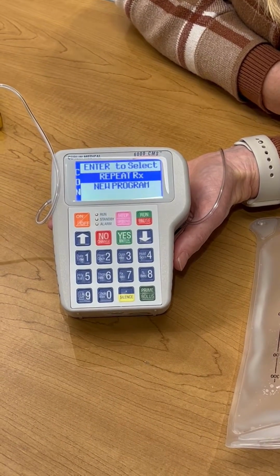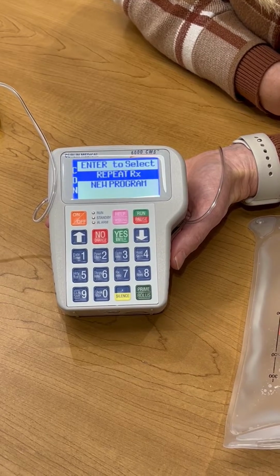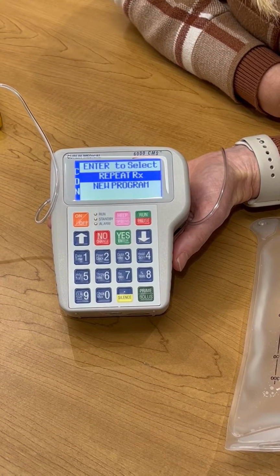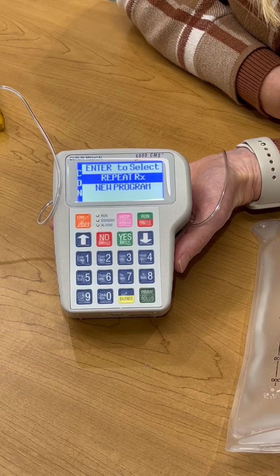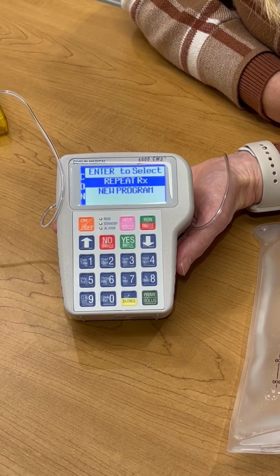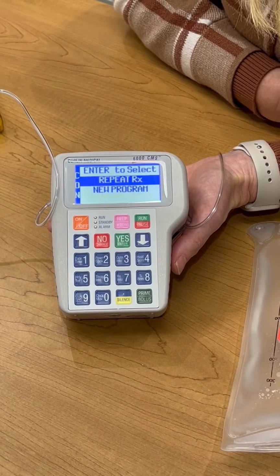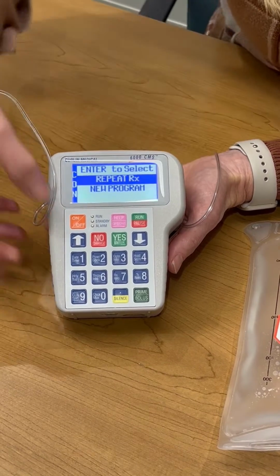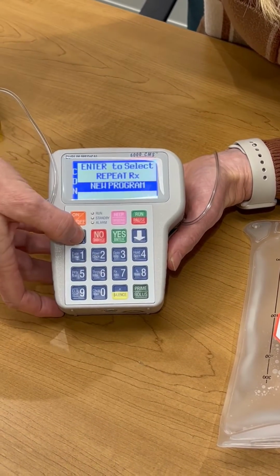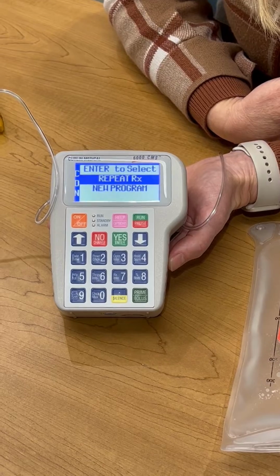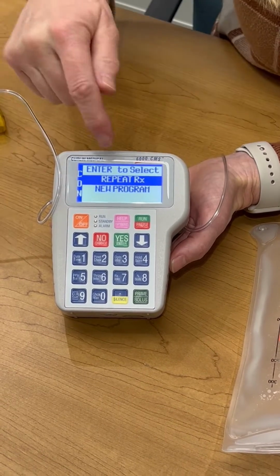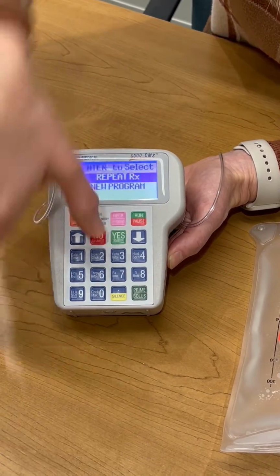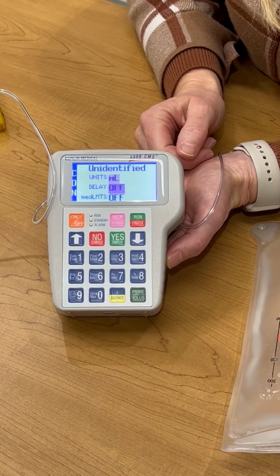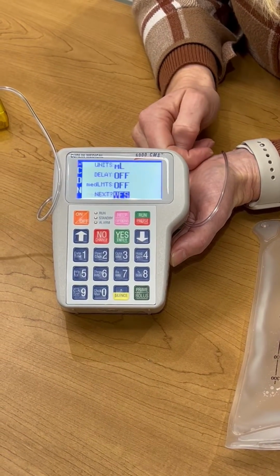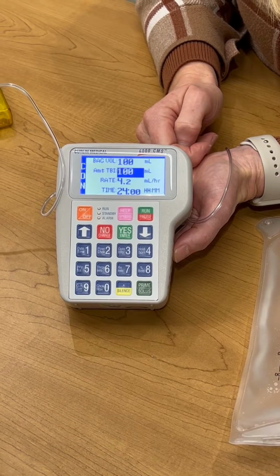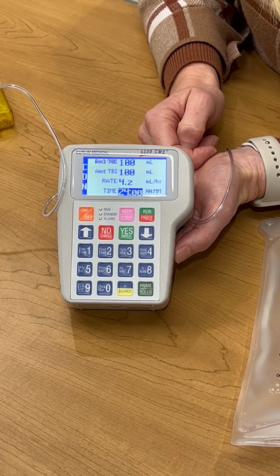If at any time that you want to turn the pump off to change batteries, when you turn it back on, it's going to highlight resume because you're resuming the same bag. If you find it's not highlighted on the correct place, you can use the up and down arrows to move that. But right now we have a new bag. Repeat RX is what I want, and that's the yes button. And this is just going to go through what the pharmacy has programmed for you. You don't have to do anything with this.